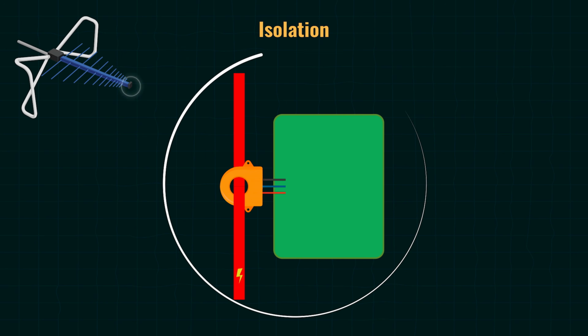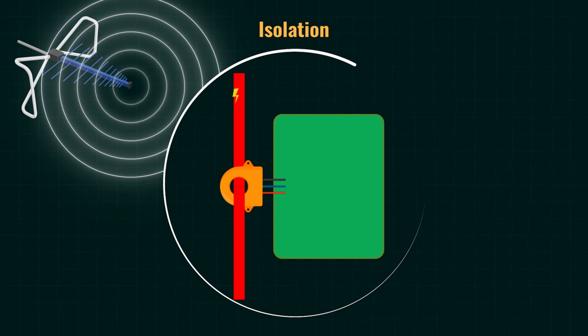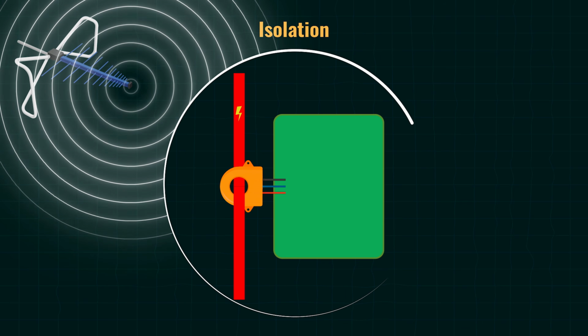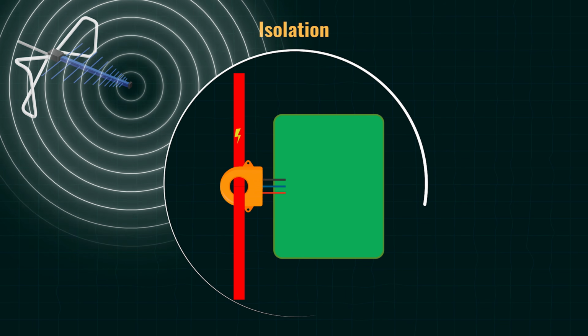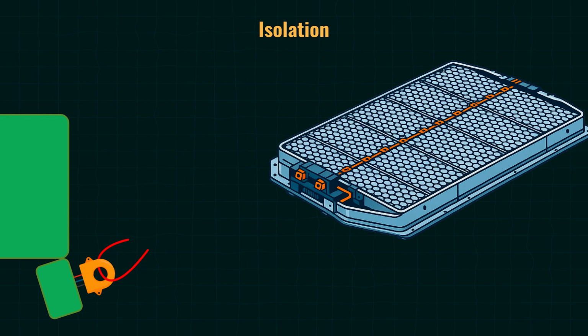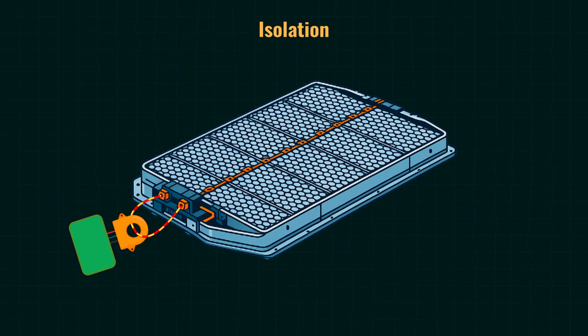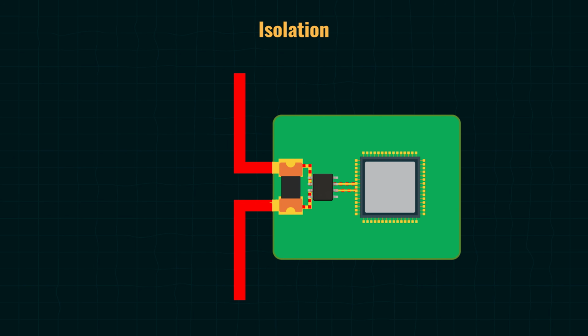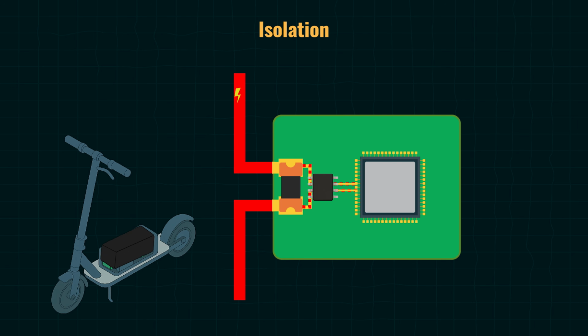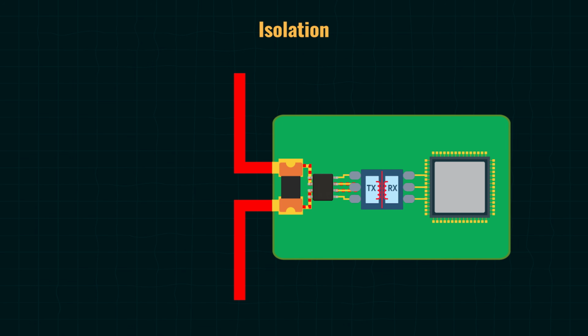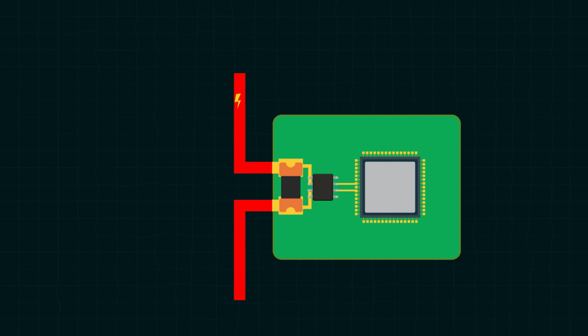Now let's look at isolation. Hall effect sensors inherently provide electrical isolation between the sensed current and the sensor output. This is extremely useful in noisy environments or when sensing on the high voltage side of a battery system. Shunt sensors, on the other hand, do not provide isolation by default. In low voltage systems, this usually isn't a problem. But in high voltage or safety critical systems, extra isolation components might be needed if we're using a shunt.